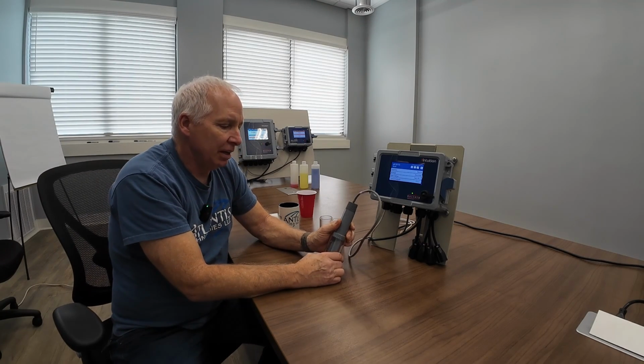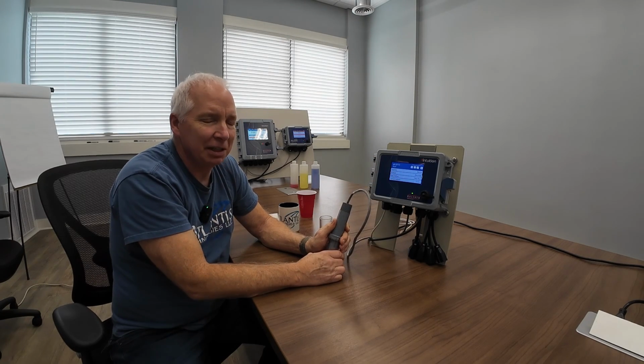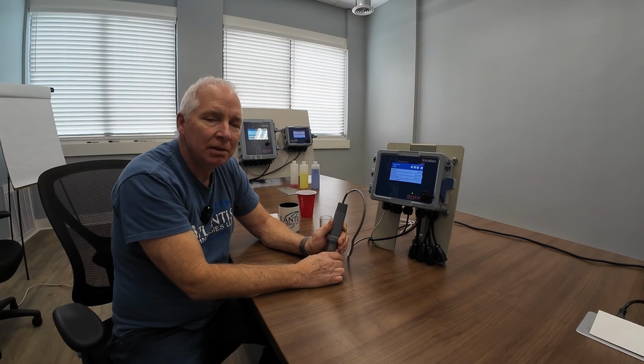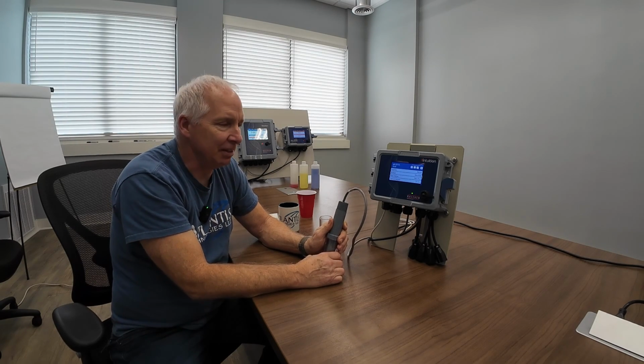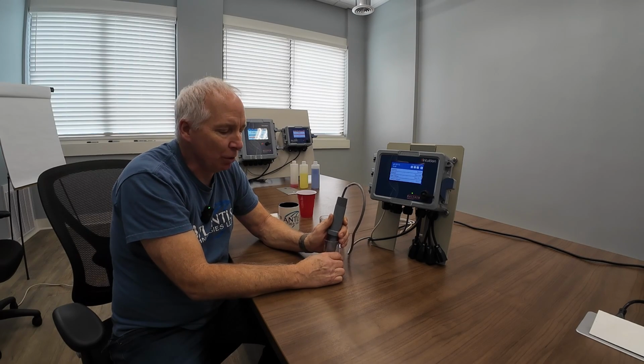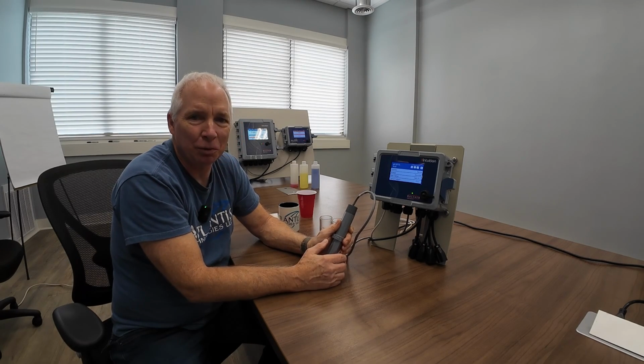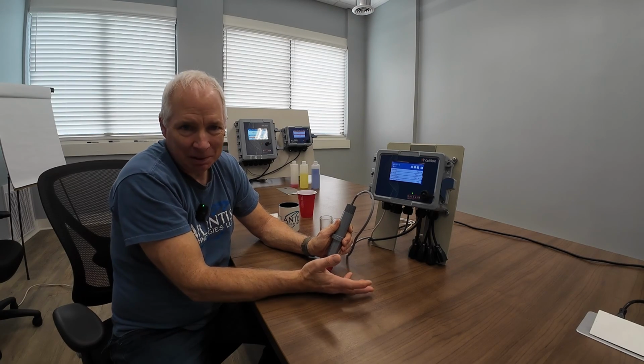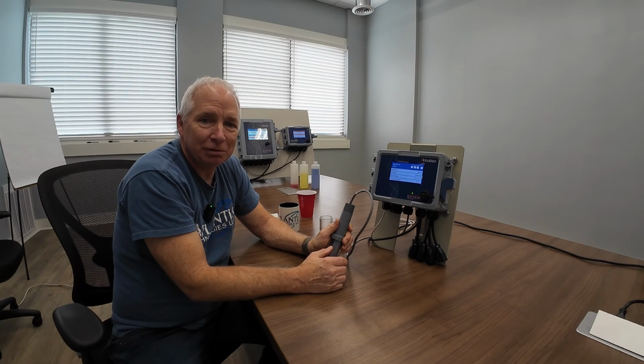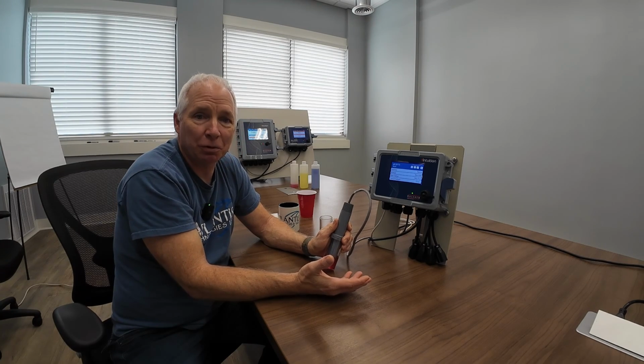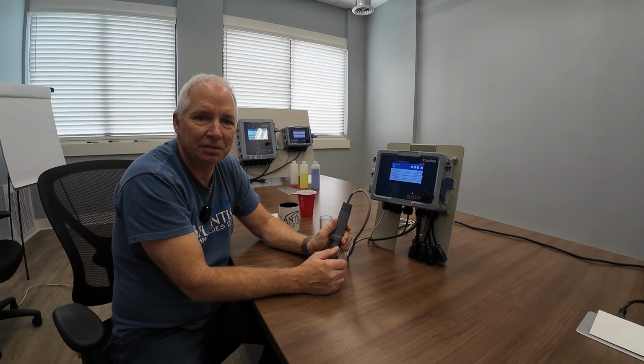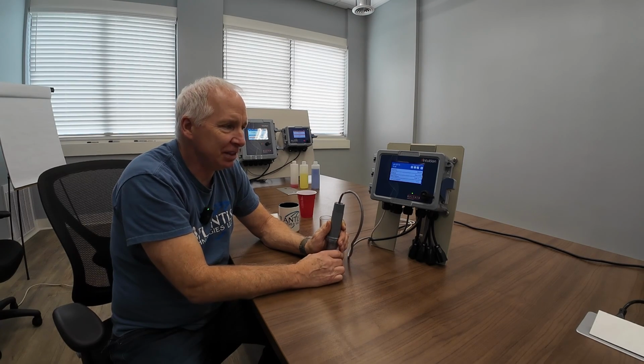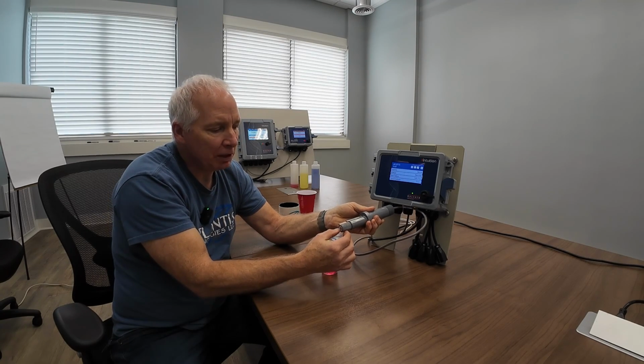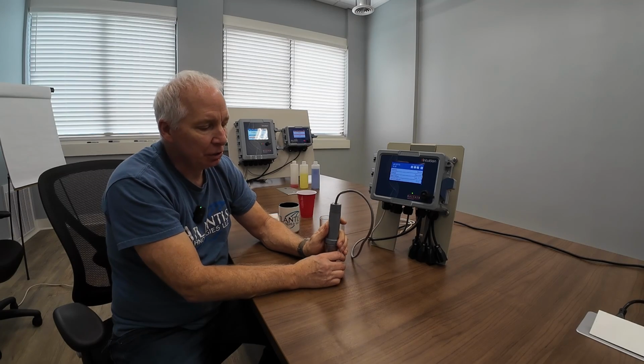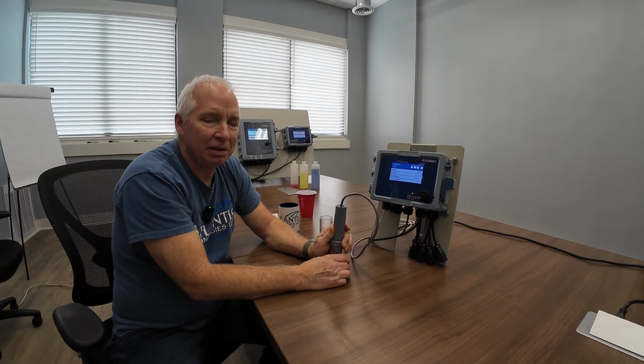The other things are, if you get a reading, you're looking at these and you see the reading seems to be way off. It's 100 off instead of the 177 or the negative 177. It's probably a good time to change the probe. These probes have a life, if you're really lucky, you might get 2 years out of it. Typically, they're about a year, but it all depends on your process. You might only get 4 or 5 months out of it if it's a really hot process, if it has something that's aggressive, that's hard on the probe, or if you have something that really starts plugging up this white junction ring there. It could shorten the life of it. So if you see that you're not getting the millivolt readings even after you've cleaned it, then it might be time to get a new housing.